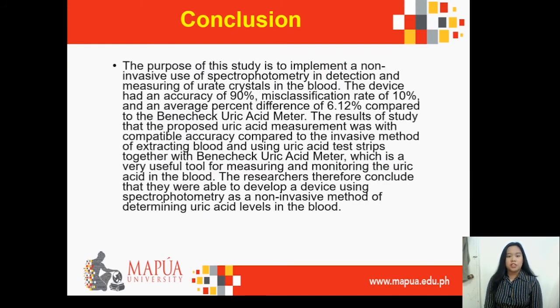So for the conclusion, the purpose of this study is to implement a non-invasive use of spectrophotometry in detection and measuring of urate crystals in the blood. The device had an accuracy of 90%, misclassification rate of 10%, and an average percent difference of 6.12% compared to the Benecheck Uric Acid Meter. The results of the study show that the proposed uric acid measurement had compatible accuracy compared to the invasive method of extracting blood and using uric acid test strips together with the Benecheck Uric Acid Meter, which is a very useful tool for measuring and monitoring the uric acid level in the blood. The researchers therefore conclude that they were able to develop a device using spectrophotometry as a non-invasive method of determining uric acid levels in the blood.